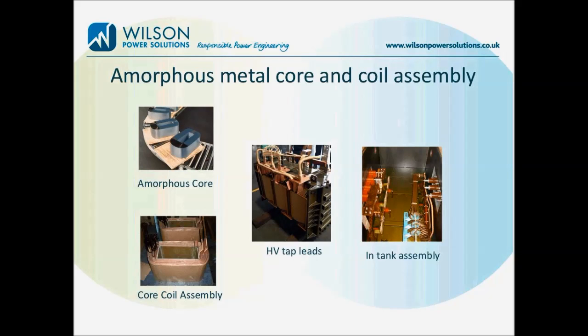Now the whole construction is clamped at the top and bottom. On the far right there, I've shown a shot where the transformer has been fitted inside the tank and covered with oil. So this is the final stage of manufacture. And on the left of that image you can see there the LV bars connected to the 4-pole LV monoblock, which goes out through the tank to the LV airbox, which contains the cables. And then there are 3 HV bushings there on the right, connected up, that go out to the HV airbox.